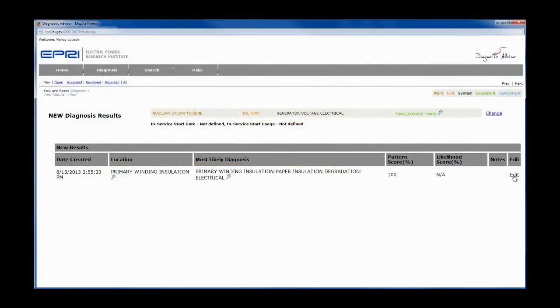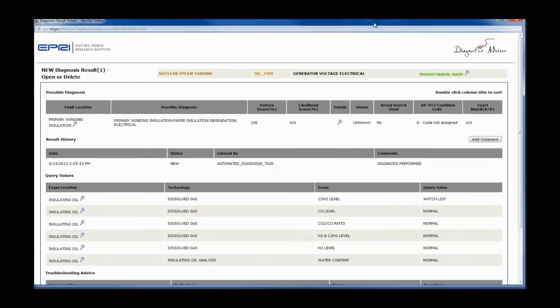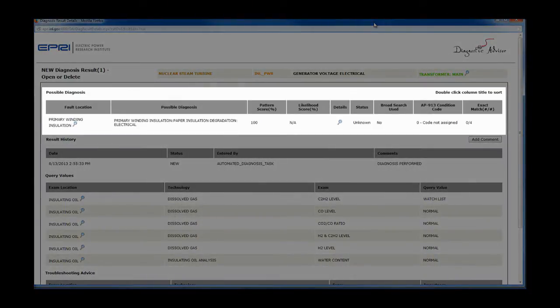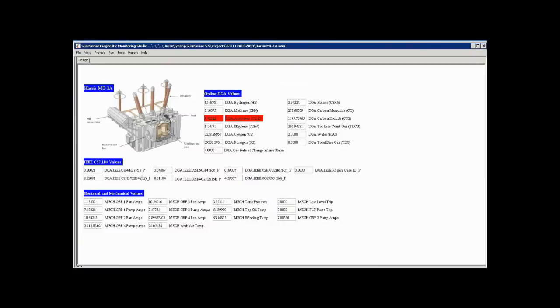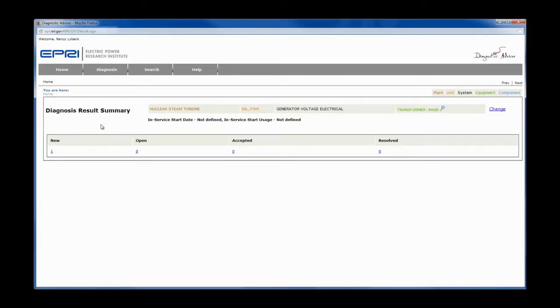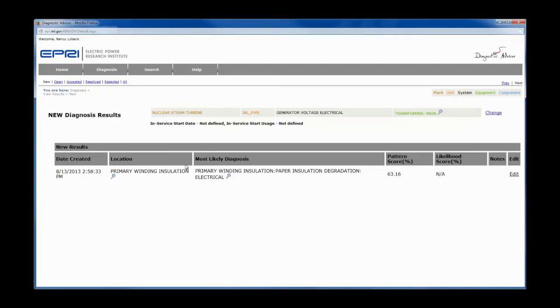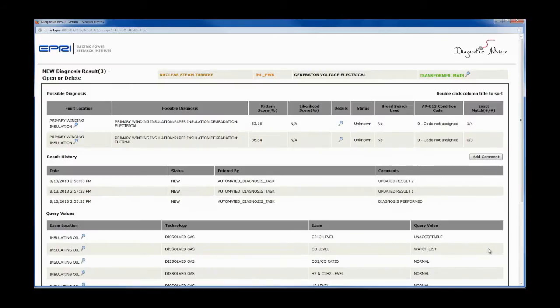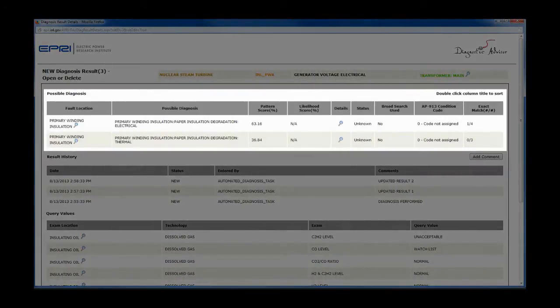A diagnosis result begins with the possible diagnosis. The Diagnostic Advisor determines which diagnosis is the best match to the available plant data. Given only the alert for increasing acetylene concentration, the electrical winding insulation degradation is the only diagnosis. As monitoring continues, an increase in carbon monoxide level is observed. The Diagnostic Advisor recognizes the change automatically and updates the diagnosis result with this new information. Notice that updated information causes a new possible fault to appear: thermal winding insulation degradation.